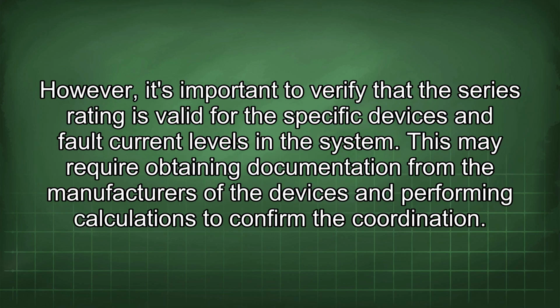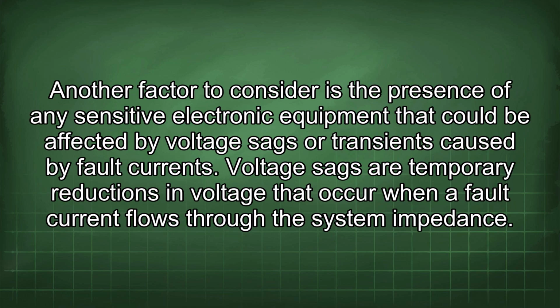However, it's important to verify that the series rating is valid for the specific devices and fault current levels in the system. This may require obtaining documentation from the manufacturers of the devices and performing calculations to confirm the coordination. Another factor to consider is the presence of any sensitive electronic equipment that could be affected by voltage sags or transients caused by fault currents.